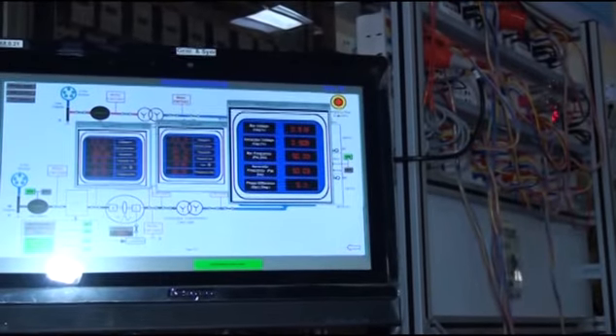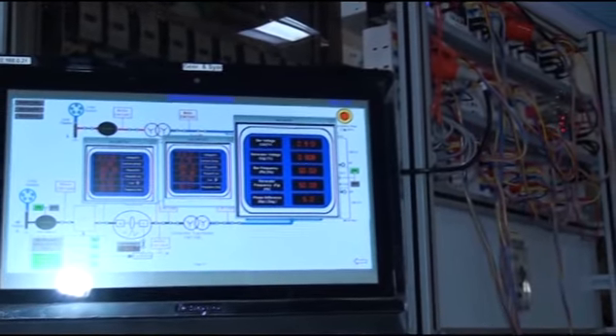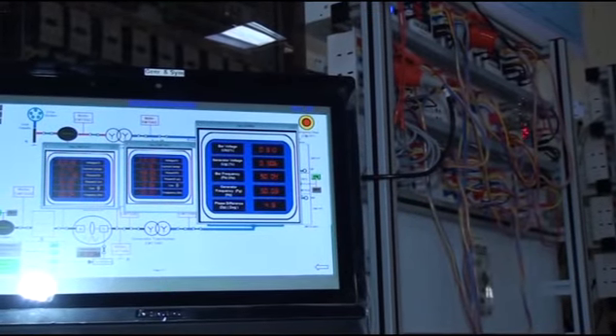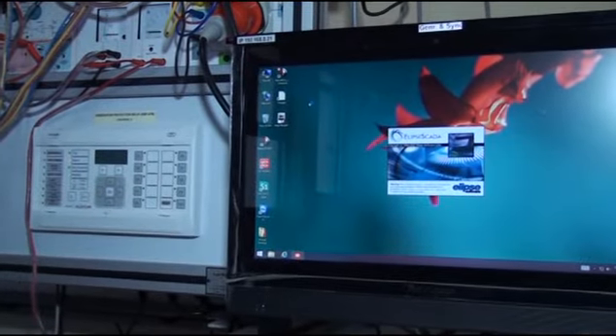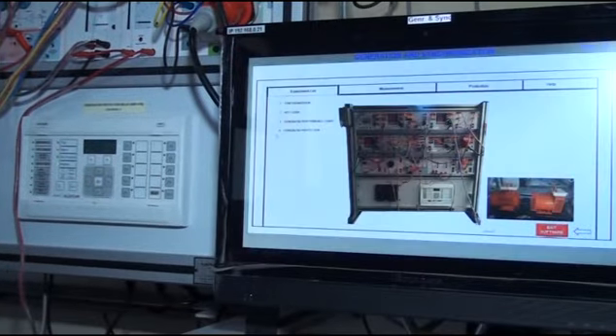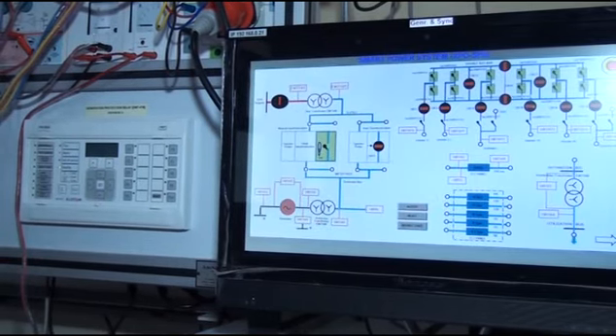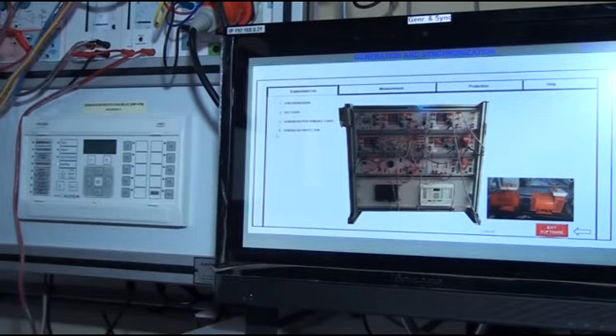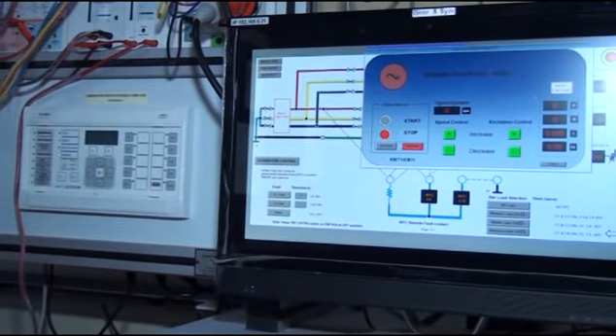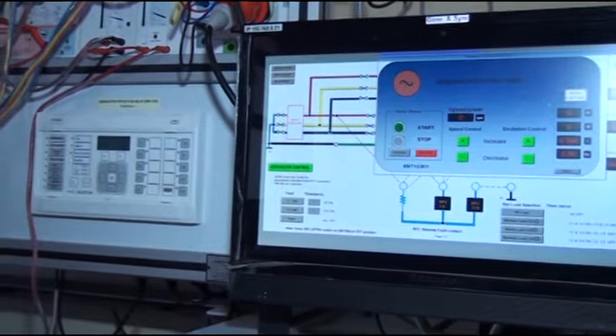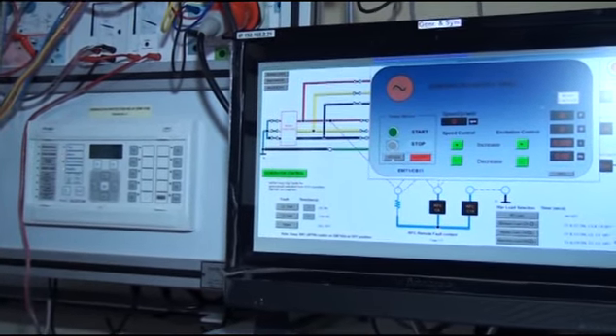After synchronization, we can control watt by the speed and power increment decrement buttons, and VAR control by the excitation voltage increment decrement buttons. Now we are performing an experiment to create a differential fault on the generator. Open the SCADA screen. This is the overall smart power system screen. Press the next button to get the experiment list. Select experiment number 4, generation protection, and you will get the generation protection screen. Now press the generator control button and observe the generator control panel screen.